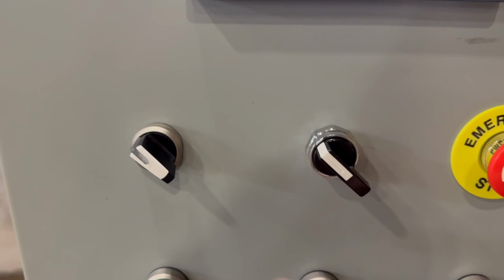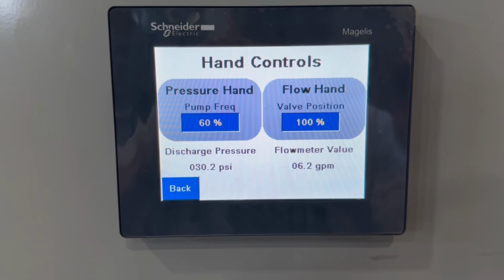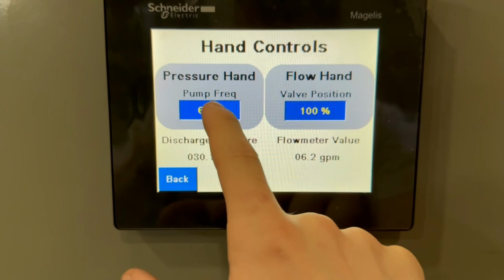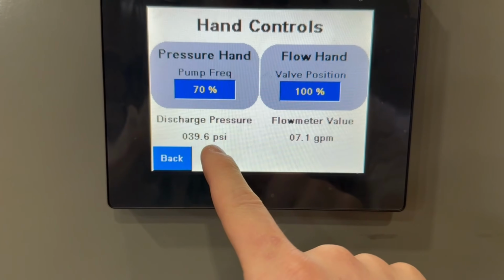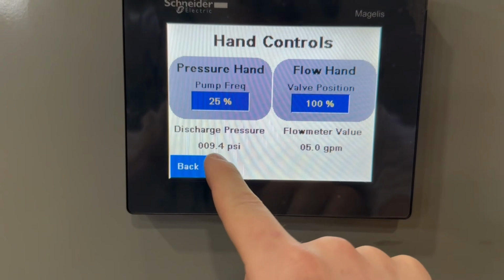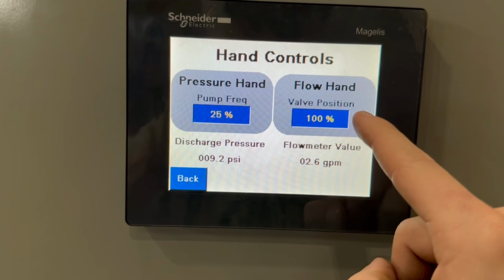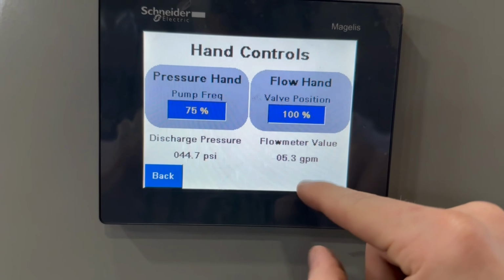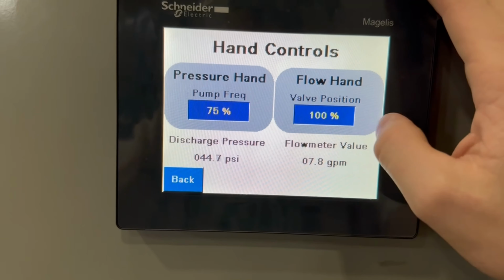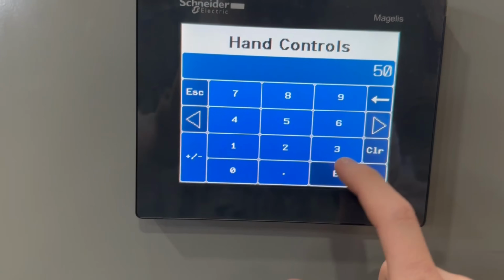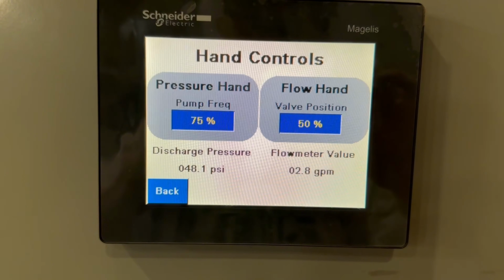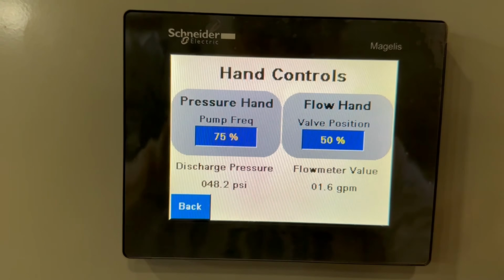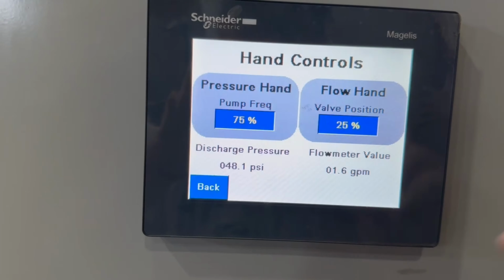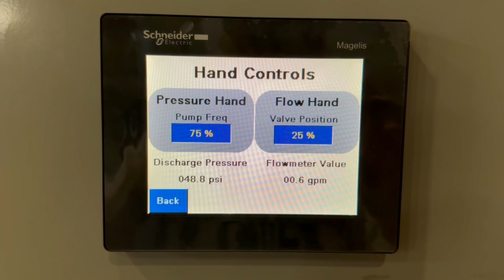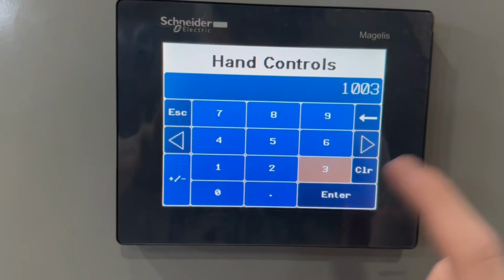Now, with both of our valve and pump in auto mode, we can see that we can change the percentage of the frequency of the pump. So from 60% we can go to 70%, and we can watch how that changes the pressure. We can send it to 25% pump power, and that changes the pressure down there. With the valve position at 100%, I'll increase this so it's easier to see. We go from 7.8 gallons per minute. We drop that to 50% closed. We get 1.6 gallons per minute. Again, 25%. And we'll switch it back to 100.